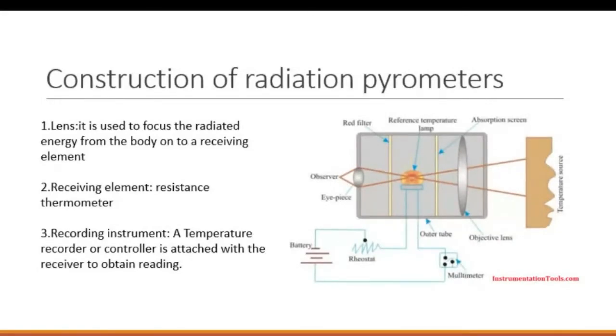Construction of pyrometers. Lens. In the construction of the pyrometer, the lens is focused. The lens is used to focus the radiated energy from the body onto the receiving element. The receiving element is a type of detector that converts the radiated energy into electric energy to detect the temperature. Recording instrument. A temperature recorder or a controller is attached to the receiver to obtain the reading.